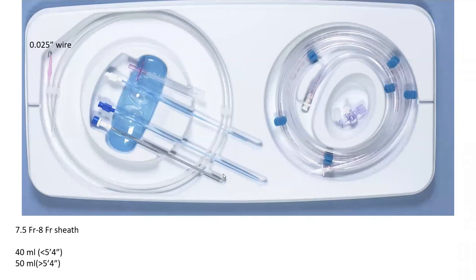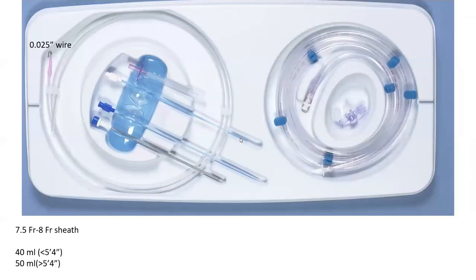Now, one additional note, in that tray, there is also another dilator that we use in case we decide to do sheathless insertion of the balloon pump. So in that case, you get your micropuncture access, you put your micropuncture sheath, and through the micropuncture sheath, you advance that 0.025 inch wire. And then over that 0.025 inch wire, you advance that special taper dilator. Then you advance the balloon pump catheter sheathlessly just over the wire. And that dilator helps you create the hole to allow you to advance the balloon pump.